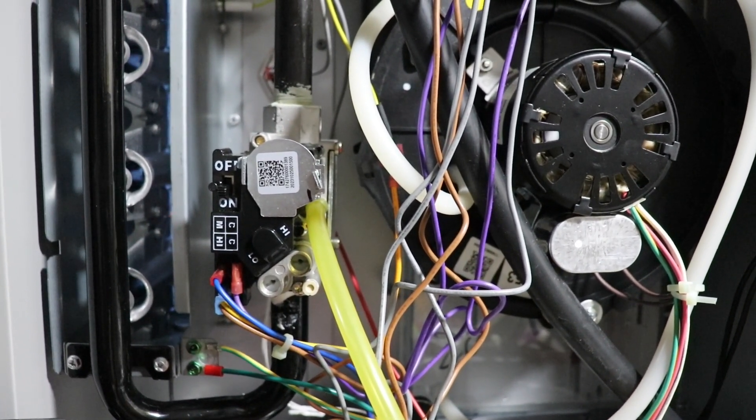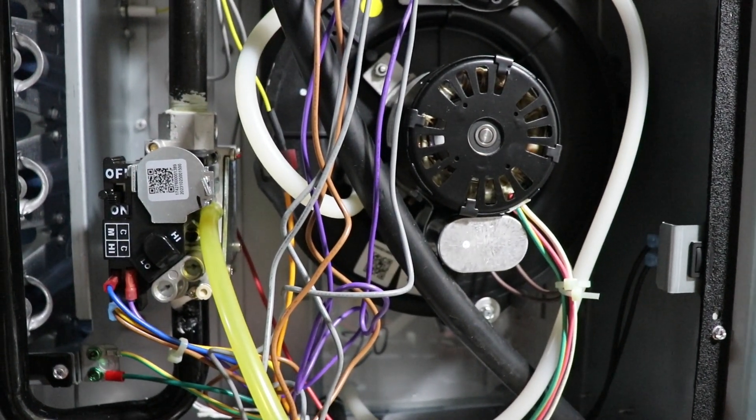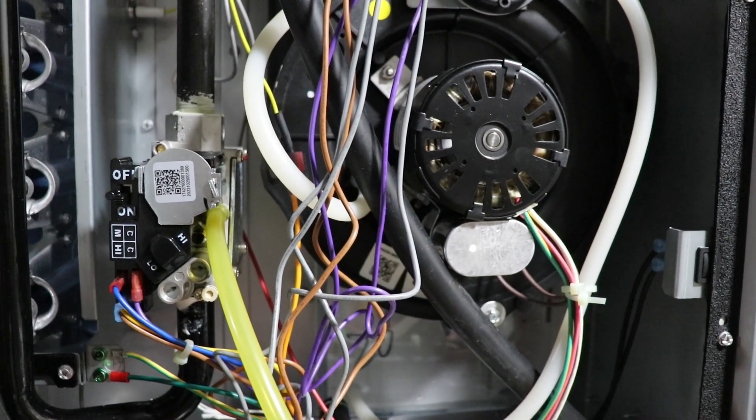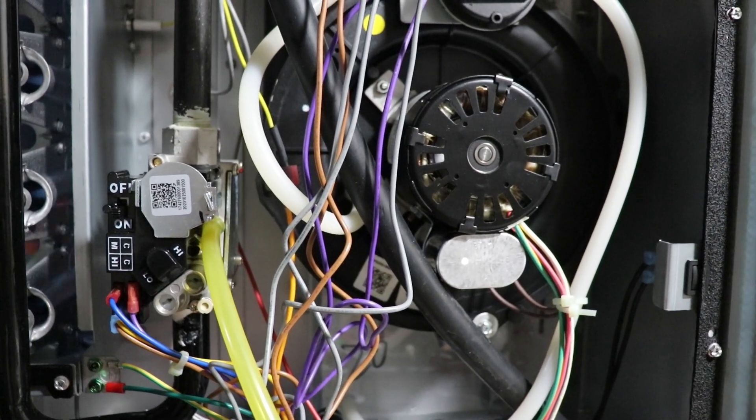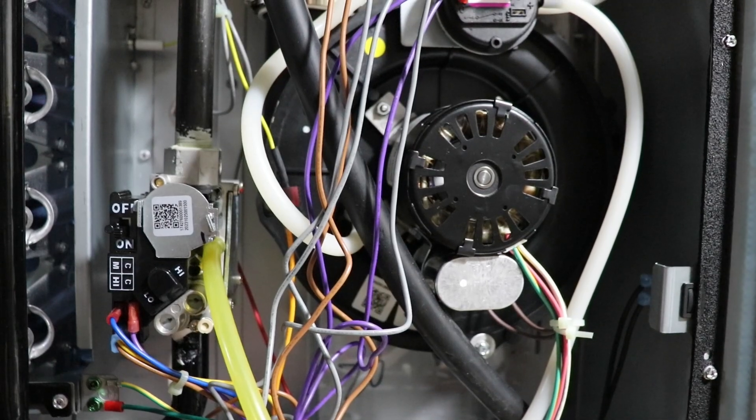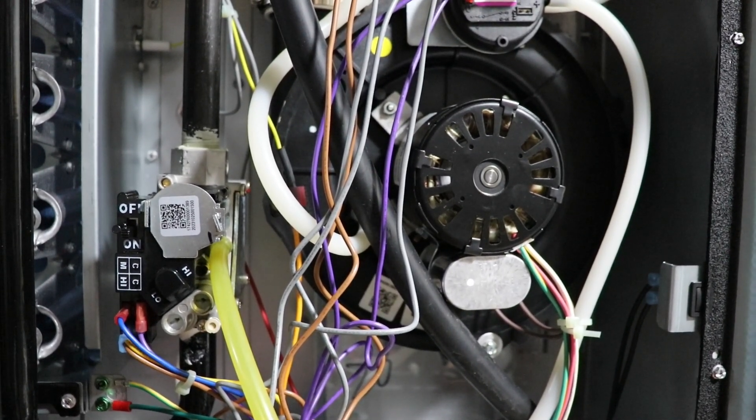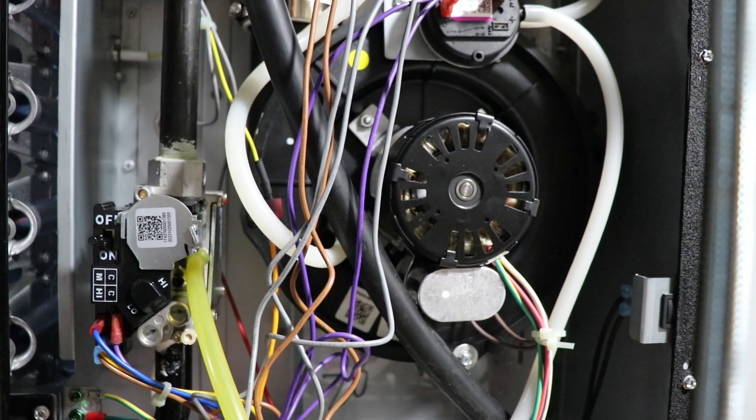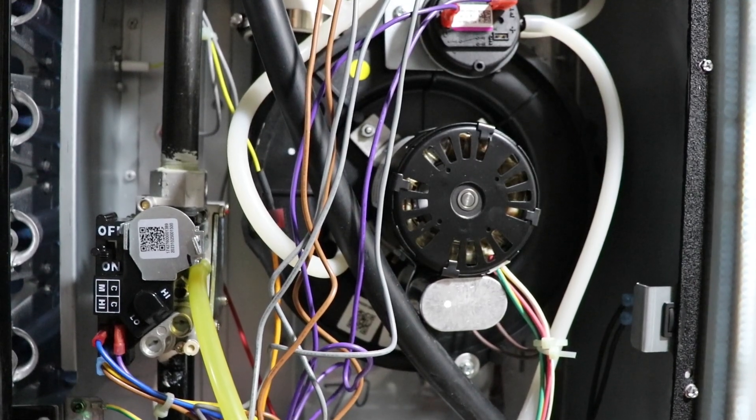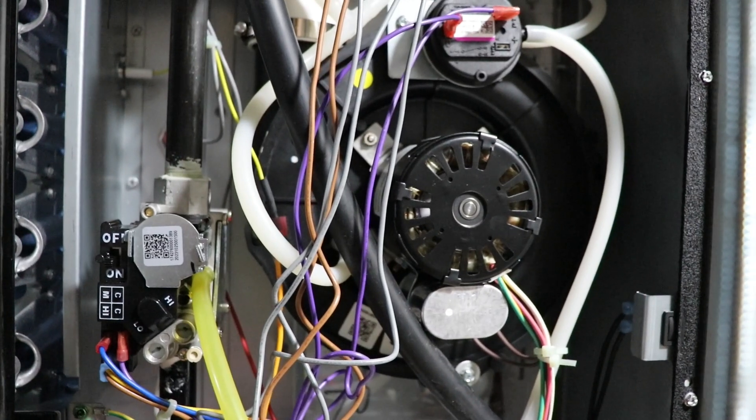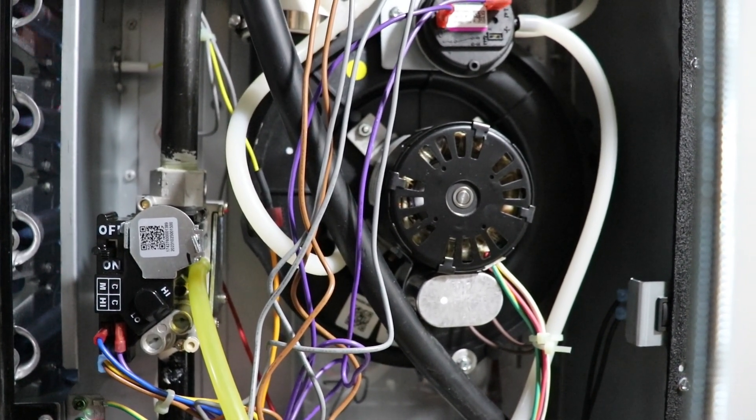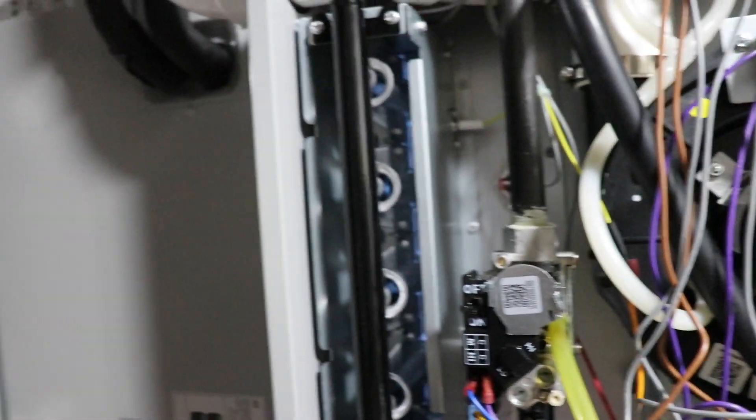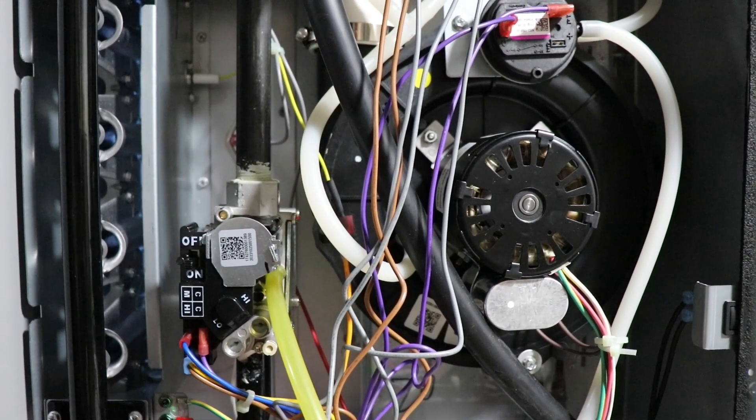You'll see that it runs like a purge on the fan after a failed run. You'll see a short trace in the Ecobee on the website information. This is for like the fan. It'll run the blower fan, and I think maybe the inducer fan as well. I'm not too sure. But that's sort of what you'll see as a signature when it does a successful failure and then it's trying to restart again. A short run. But the temperature will continue to drop, and it's not trying to run the compressor side of things either. You're going to continually lose heat in the home.